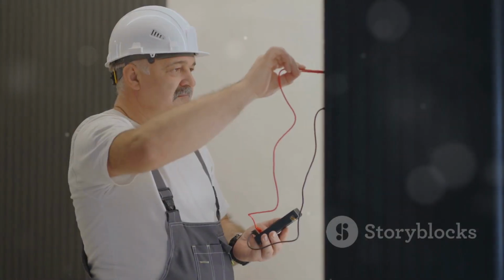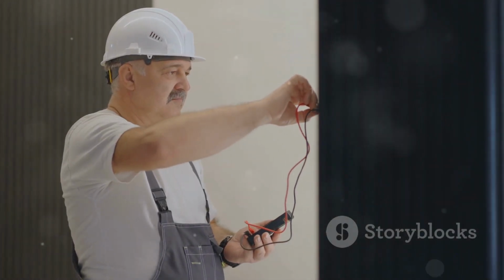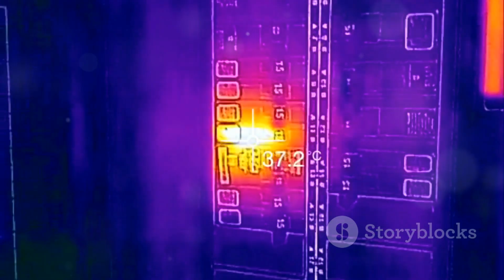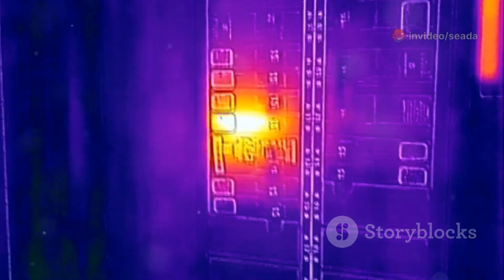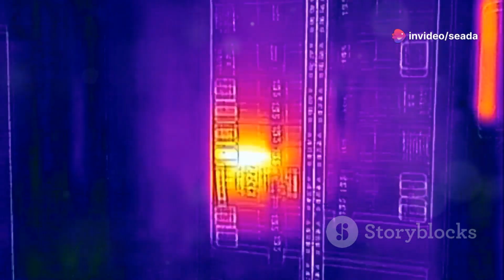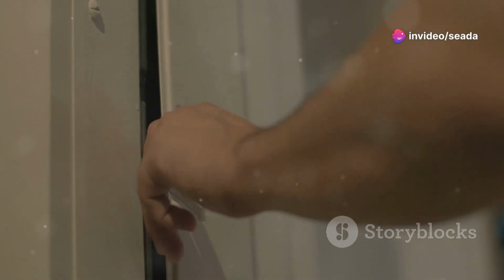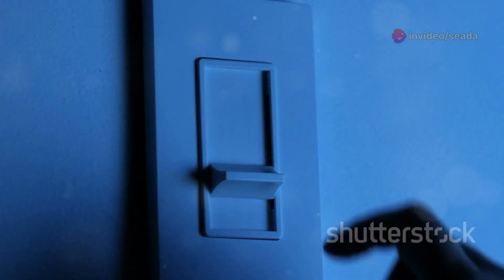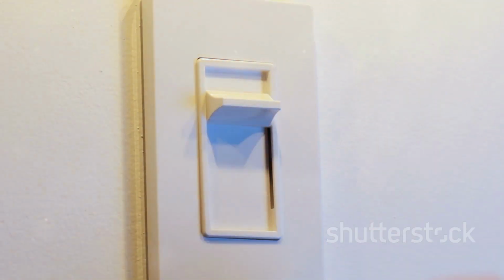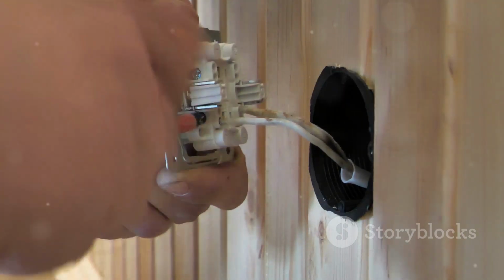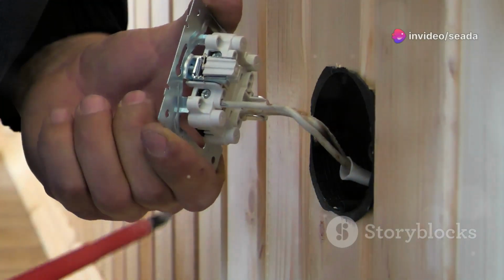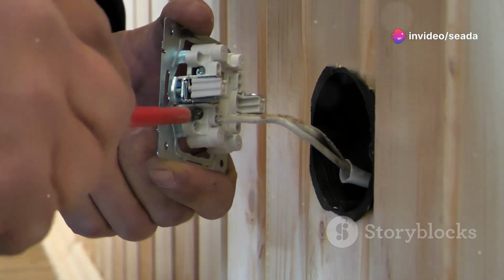Most electrical problems aren't catastrophic. They're caused by loose connections. Loose wires create resistance, which generates heat, a major fire risk. The neutral bar is a common trouble spot. If a neutral wire is loose, you'll see flickering lights or dimming when appliances run. MCB terminals can also loosen, causing isolated issues like dead sockets in one room.